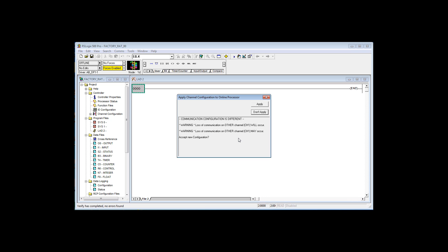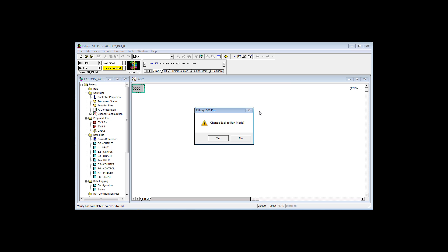Now this is an important message. Communication configuration is different. Well I can tell you right now that channel 1 in that controller, that's Ethernet, it's 100 100 100 probably 226 or something like that. So what's going to happen is if I say don't apply, then that IP address that I just showed you that I put in there 100 100 100 86 will not download. It'll leave the IP address that's already in the controller. I think what I'll do is say don't apply, just so you can see the difference.